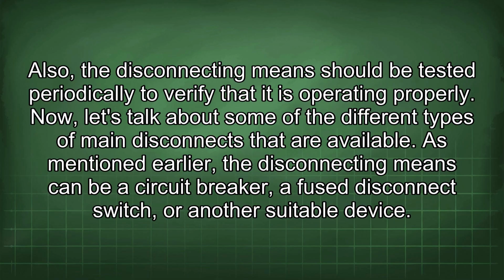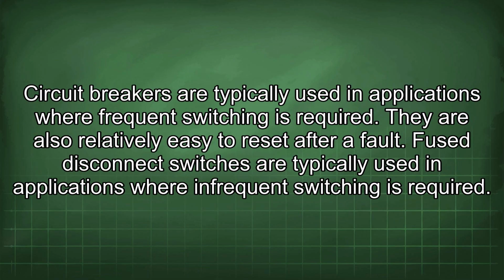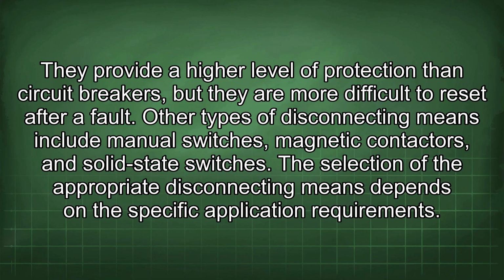Now, let's talk about some of the different types of main disconnects that are available. As mentioned earlier, the disconnecting means can be a circuit breaker, a fuse disconnect switch, or another suitable device. Circuit breakers are typically used in applications where frequent switching is required. They are also relatively easy to reset after a fault. Fuse disconnect switches are typically used in applications where infrequent switching is required. They provide a higher level of protection than circuit breakers, but they are more difficult to reset after a fault. Other types of disconnecting means include manual switches, magnetic contactors, and solid-state switches. The selection of the appropriate disconnecting means depends on the specific application requirements.